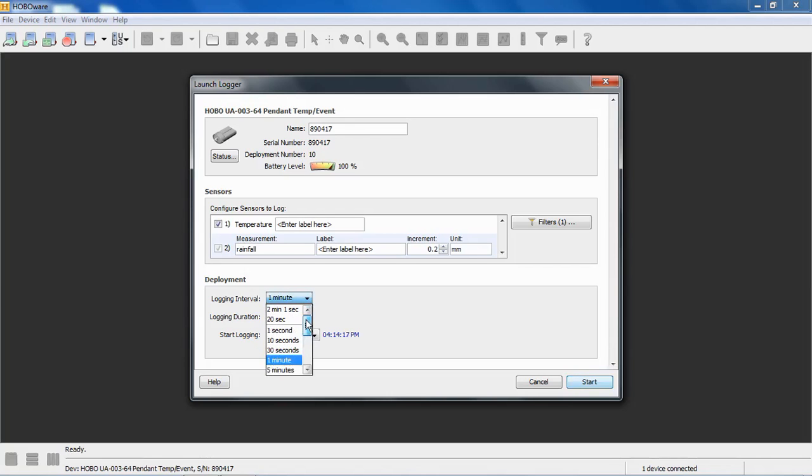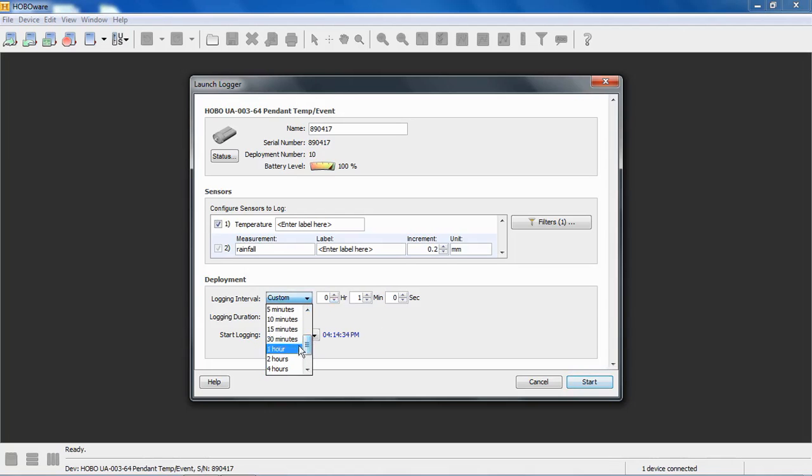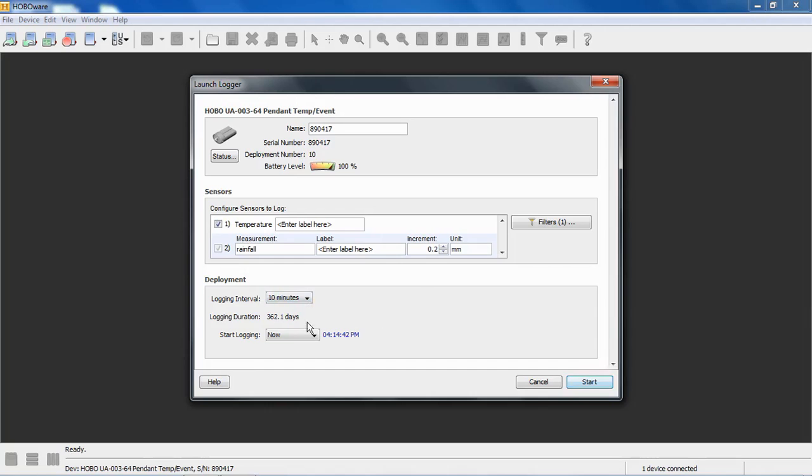We have several different common intervals to choose from, or you can put in a custom interval anywhere between once a second to once every 18 hours. Let's set a 10 minute logging interval. So here, if we're measuring temperature and rainfall at a 10 minute interval, the logger will log for 362.1 days. Keep in mind when you have a logging interval selected, that's only for the temperature channel.